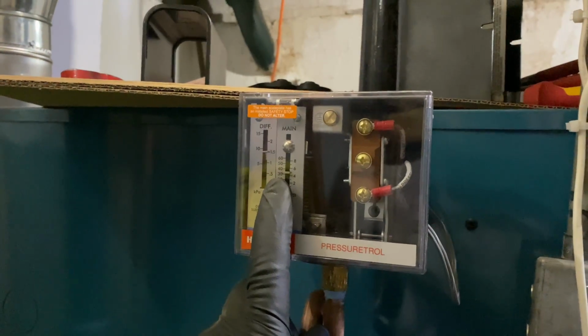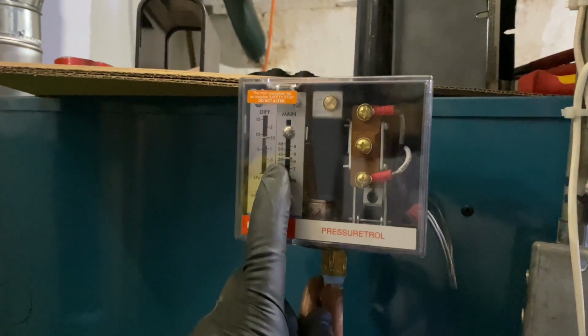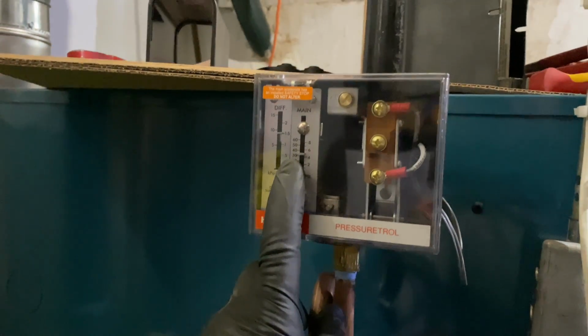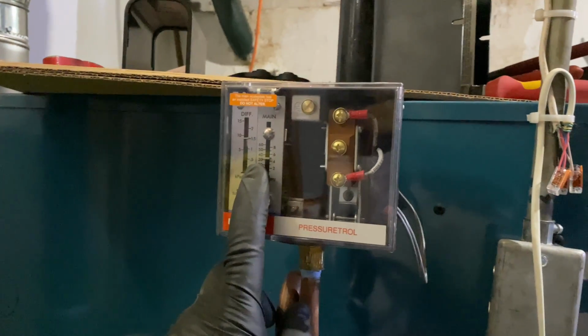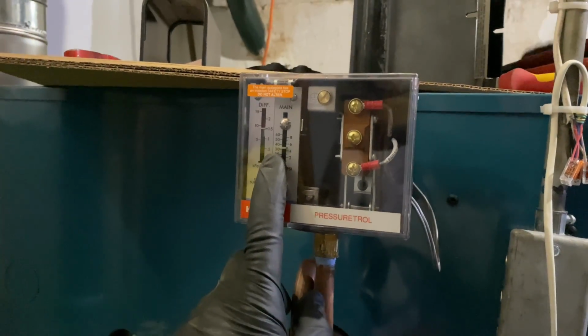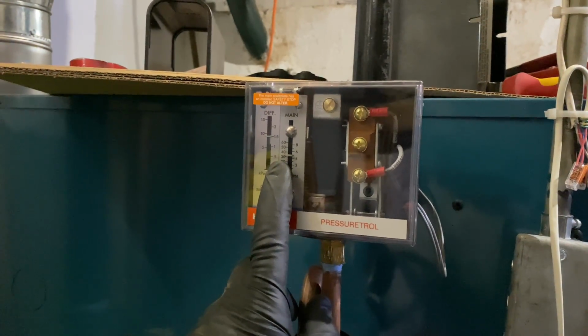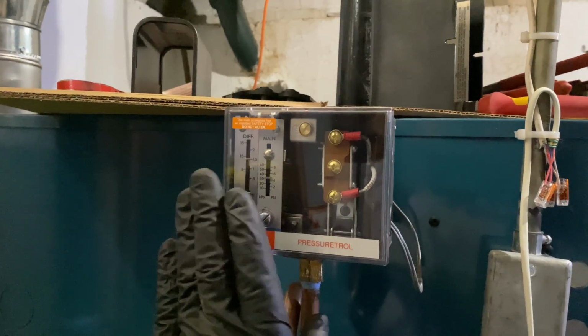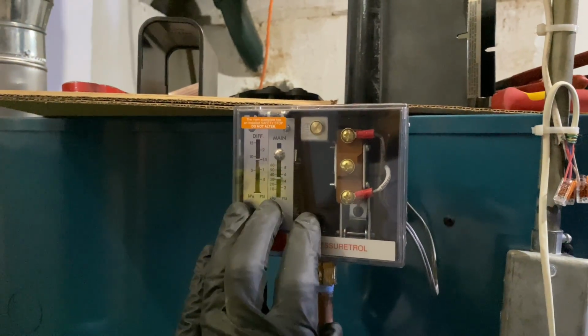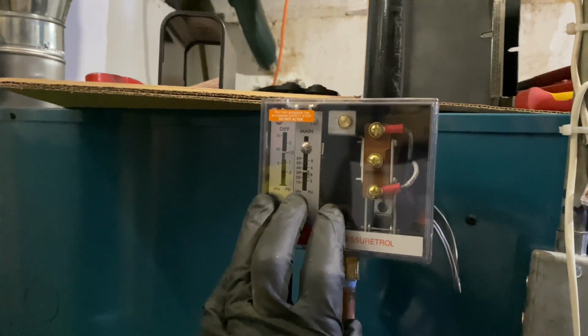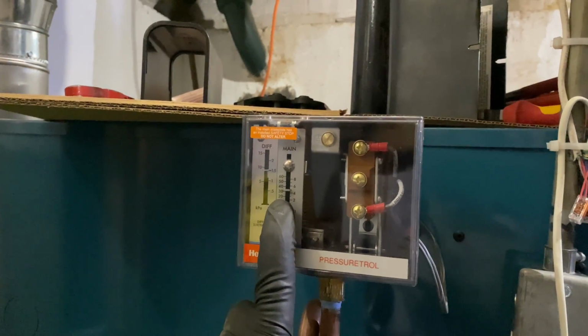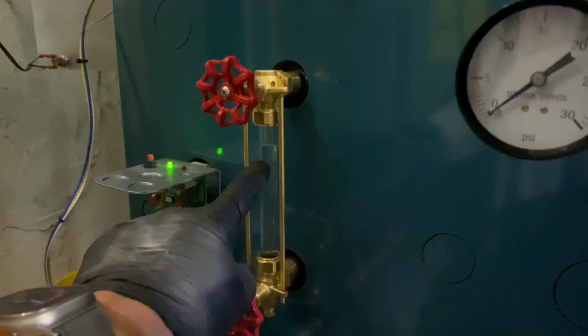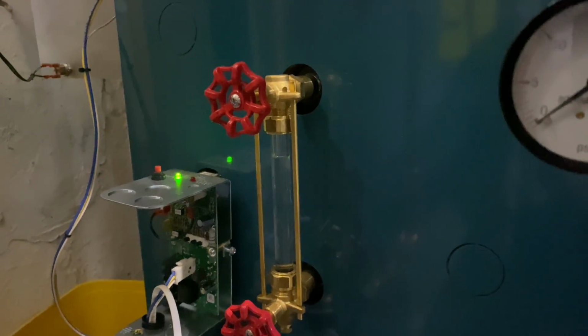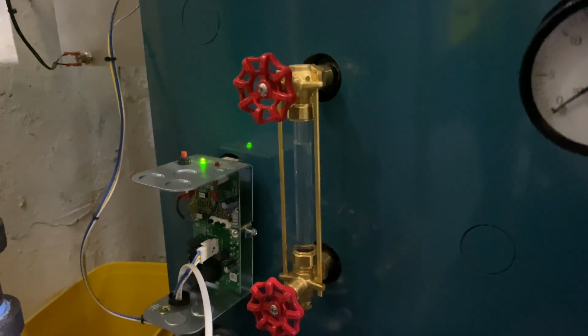All right, and if you want to look at guys like a DIY HVAC guy who likes to use a digital manometer to save you fuel, money, because you're using less pressure to give you less BTUs, just saying, if you lower the gas pressure, now you have less BTUs than what it's rated for. So on a steam system, we don't need 4.5 psi of pressure. Yeah, I guess we can stop it right there. We're about 3/4, 7/8 full around there. That's perfect. On a steam system, we don't need that much pressure.